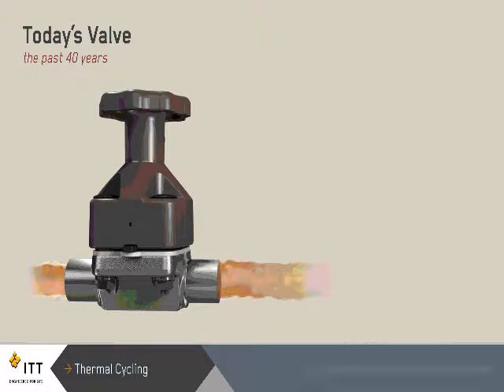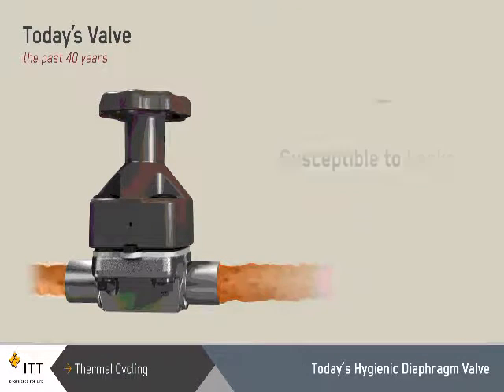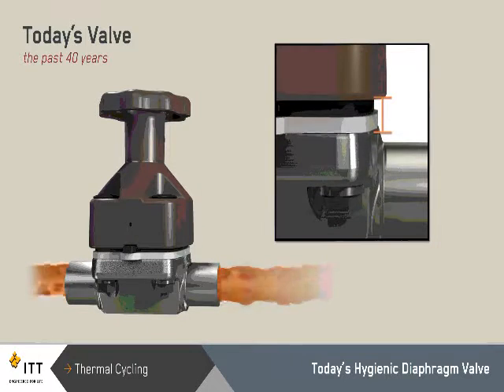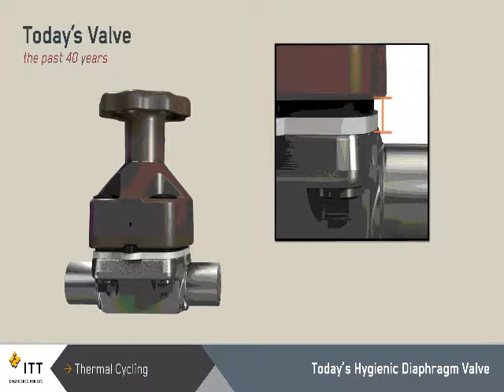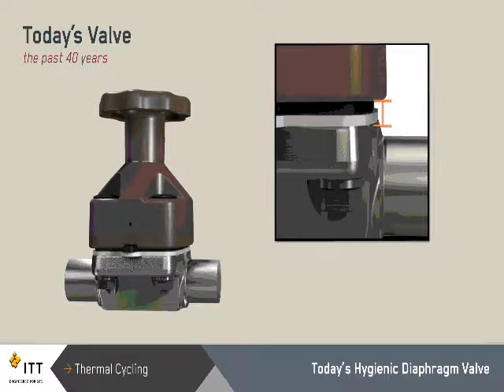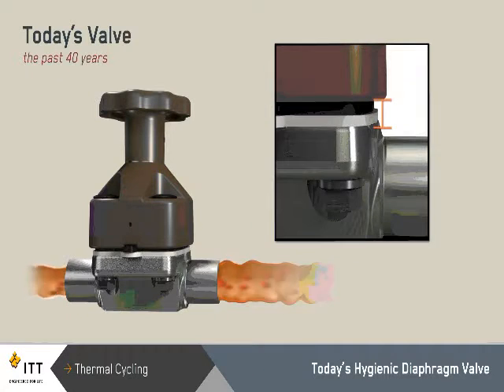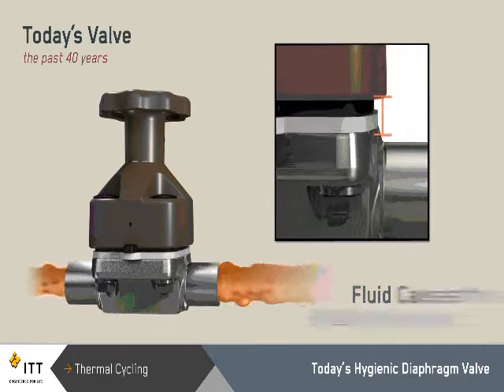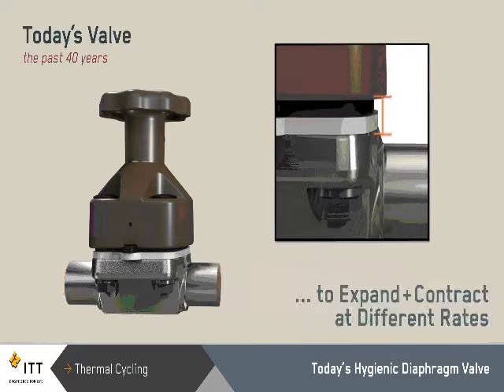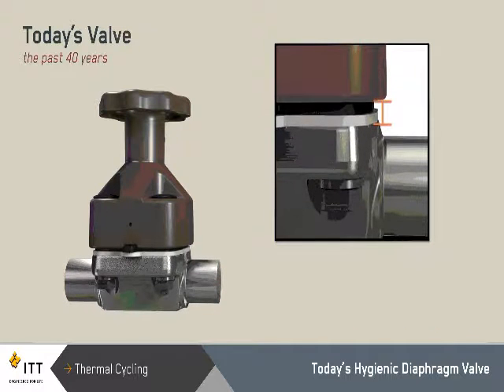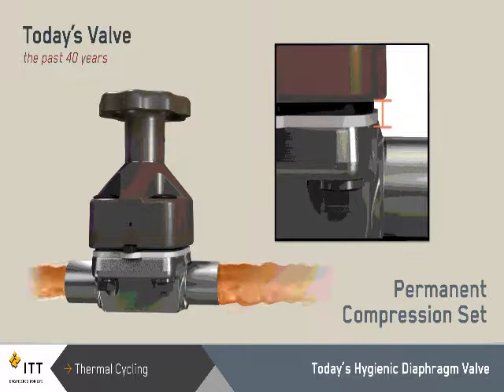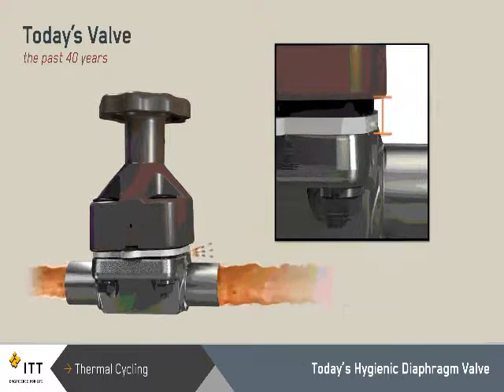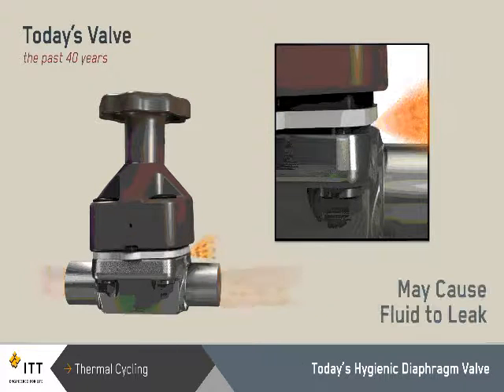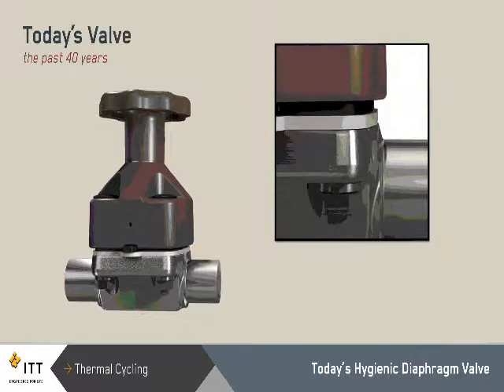Today's hygienic diaphragm valves are susceptible to leakage when the seal between the valve body and diaphragm is compromised during thermal cycling, especially for valves with PTFE diaphragms. Hot process fluid flows through the valve during the steam in place and clean in place processes. This hot fluid causes the bolts and diaphragm to expand and contract at different rates. During each thermal cycle, the diaphragms are compressed and the materials take a permanent compression set. This thermal cycle-induced compression set may eventually cause fluid to leak between the valve body and diaphragm.